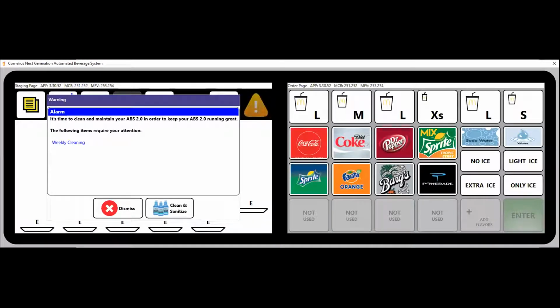If you were in front of an ABS 2.0, right now you'd see an alarm on the screen letting you know that the weekly cleaning is currently needed. At this moment you could either dismiss it or proceed with the clean and sanitize process for this specific PM. In the background there's a flashing symbol tied to the PM maintenance for the ABS 2.0. If any cleaning procedures haven't been done, this will flash at all times as an indicator that cleanings need to be done.